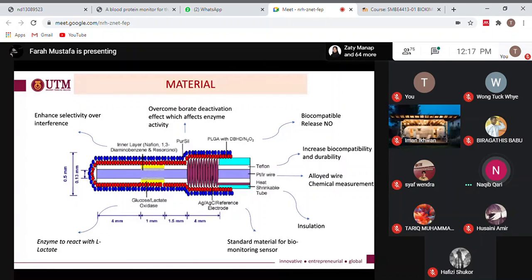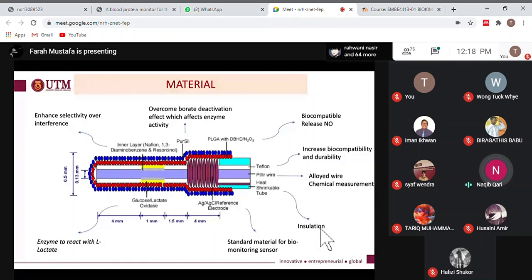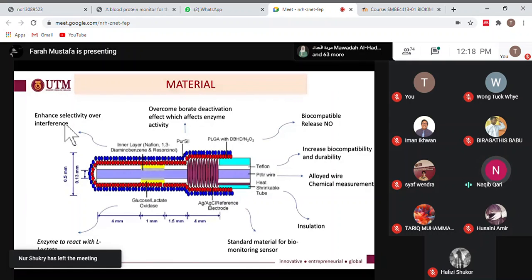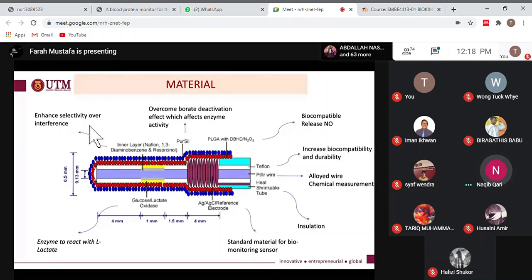So for the materials, the first would be the platinum iridium wire, which is an alloy wire used for the chemical measurement. After that, it will be coated with Teflon, which increases the biocompatibility and also the durability. There is also a heat shrinkable tube, which is used as insulation. The silver and silver chloride reference electrode is a standard material for biomonitoring sensors. So the lactate oxidase is the enzyme that will react with lactate, and the inner layer of Nafion, diaminobenzene, and also resorcinol will enhance the selectivity over other neutral molecules like ascorbic acid and acetaminophen to remove the interference.